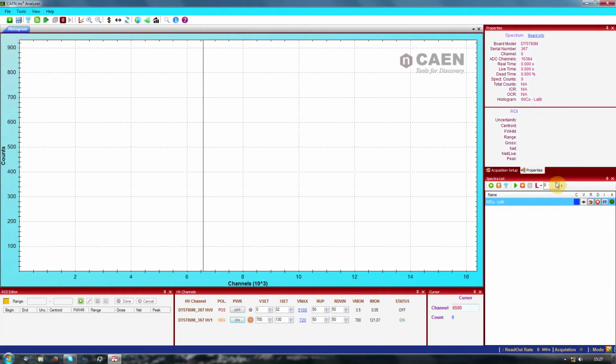We now set a limit on the acquisition lifetime of 300 seconds. In this way, the spectrum is filled until the lifetime is below 300 seconds, and this criterion is applied only on the channel we selected. We now start the acquisition and we apply the spectrum autoscale on the toolbar to better observe the spectrum.